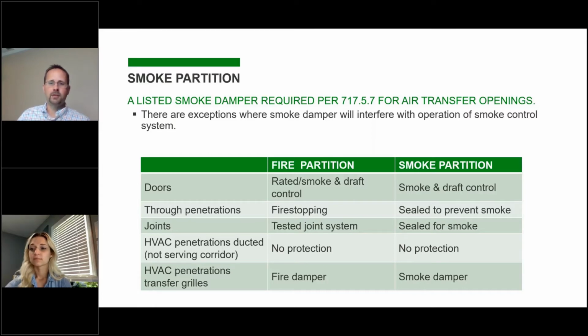And we'll talk a little bit later about incidental use spaces. Those are constructed as smoke partitions and possibly a fire barrier. So those are an area that may be in a part of a building where you would have plenum return, where you need to look at transfer openings and whether or not a smoke damper would be needed at that point.